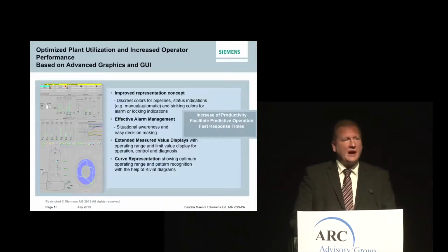On the other side, we also have to have a kind of effective alarm management. Whatever can happen in a huge plant — if I'm looking at a power plant with more than 40,000 I/O points, if something goes wrong, it will not come as a single message, you will suddenly have hundreds of messages. How can an operator really work with this overload of messages? So an effective alarm management that gives the right message right in time, and selects up front which are the important messages shown on top and which are the less important ones shown in the back — this really optimizes the plant and increases operator performance dramatically.